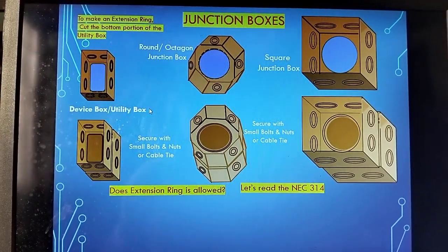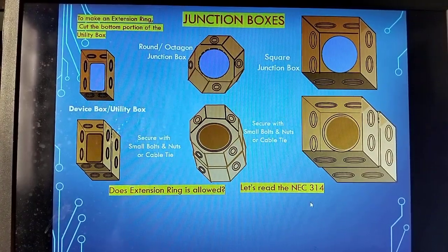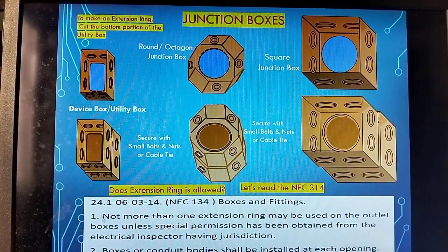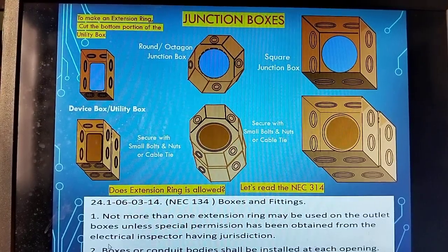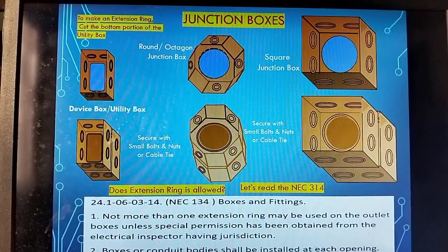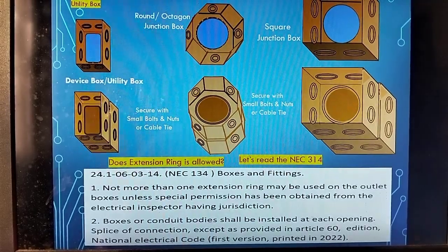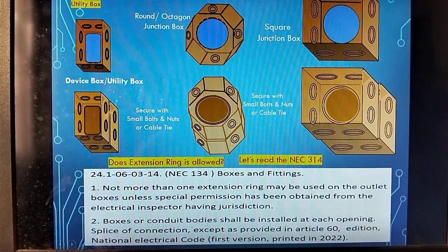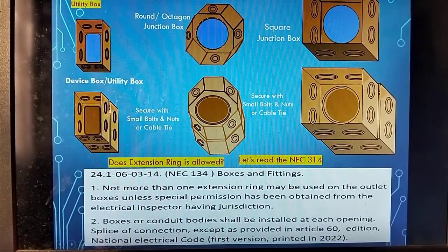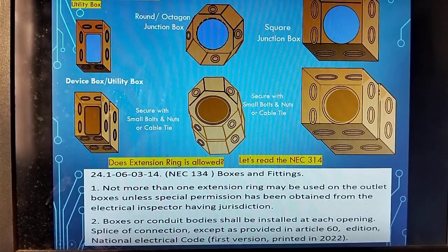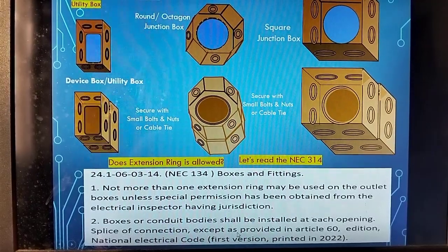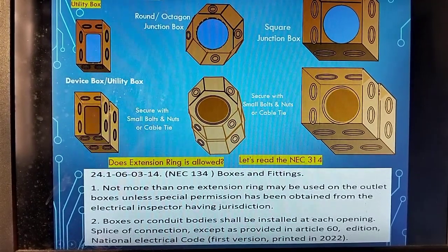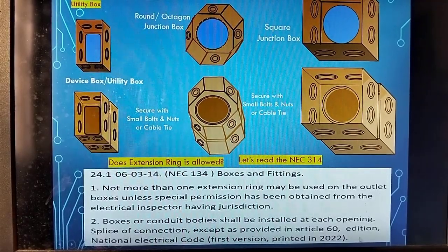Let's read the NEC, or National Electrical Code, 314. See? It says here, not more than one extension ring may be used on the outlet boxes unless special permission has been obtained from the electrical inspector having jurisdiction. Boxes or conduit bodies shall be installed at each opening, splice or connection except as provided in Article 60, edition National Electrical Code, first version printed 2022. So meaning this is allowed.